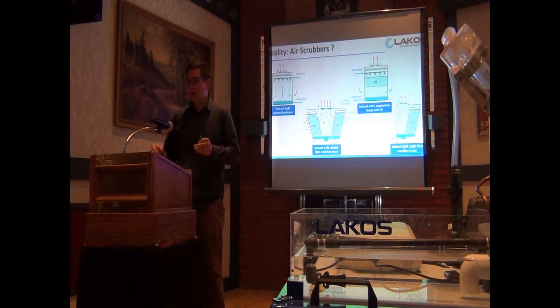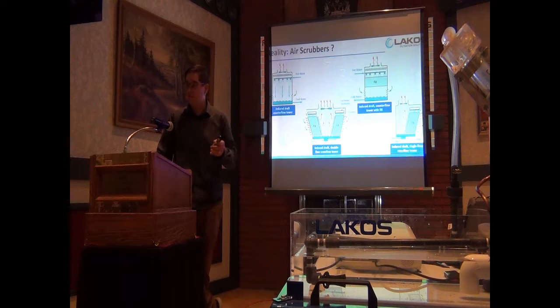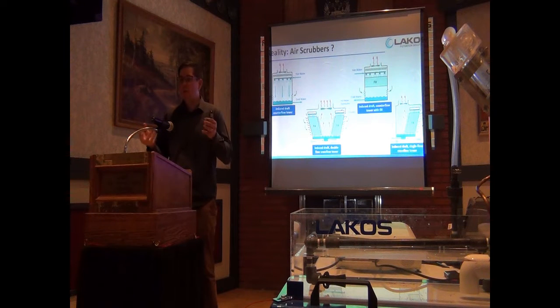A cooling tower, no matter the type, brand, make, model, they all operate very similarly. They are essentially a large air scrubber. The cooling towers pass air over top of a fill media, and at the same time there is water passed over that fill media, and through latent heat of evaporation, your cooling tower evaporates a small amount of water and cools the condenser water that's flowing through it. That's how you achieve your cooling, and then pass that condenser water down into your chiller. Now, as it's operating, when the air comes in contact with your water, your cooling tower becomes a large air scrubber. So any dirt, debris, bugs, cotton fluff, poplar fluff, all of that will get washed out of the fluid and will collect down into the cooling tower basin.